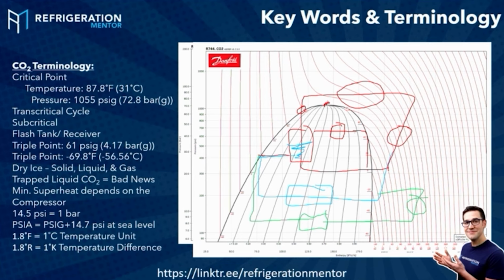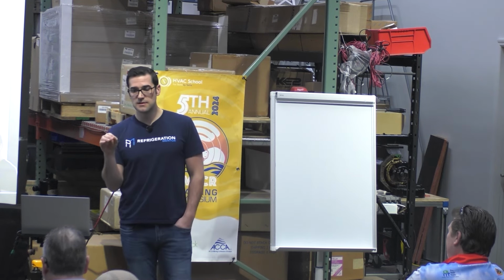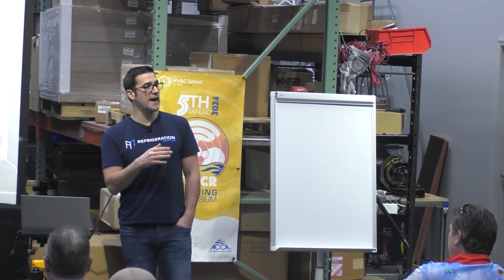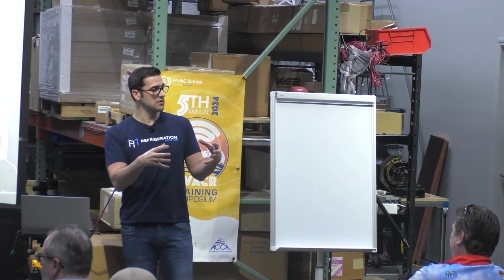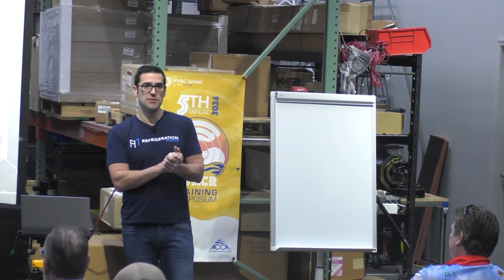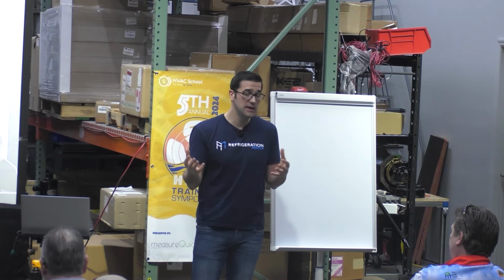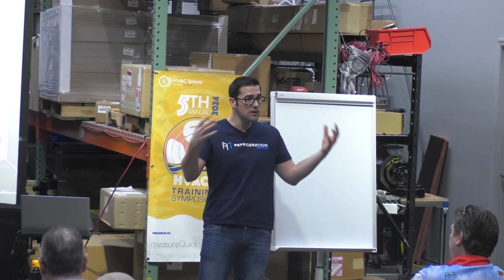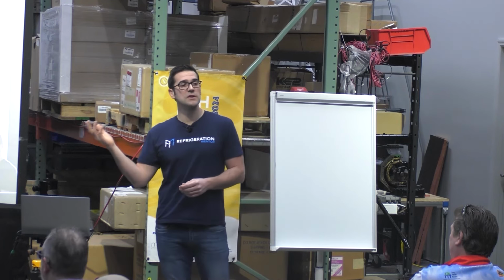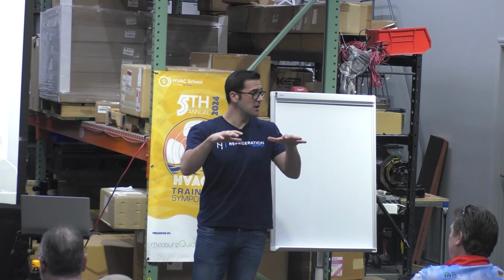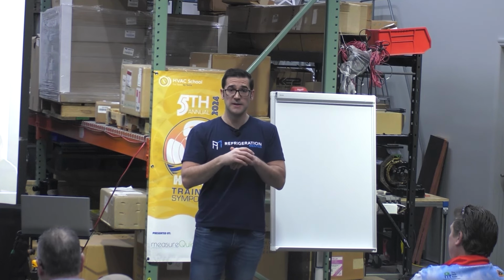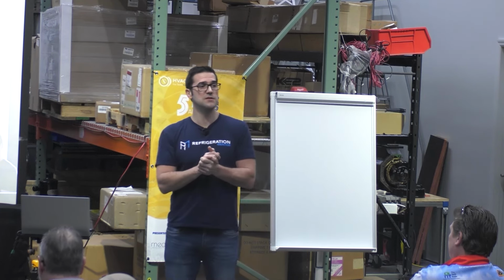We're going to talk about a few more. There's one called the triple point. Write this down. The triple point's important at 61 psi, I think it's 4.1 bar. This is the triple point. When you're below that and you have liquid CO2, it turns into something called dry ice. Anybody ever use dry ice at Halloween, put it in some water and it boils over? Well, that's what will happen. So what you need to do in a CO2 system, you've got to bring the pressure up above that 61 psi with vapor, and then you can use liquid CO2 in that system.